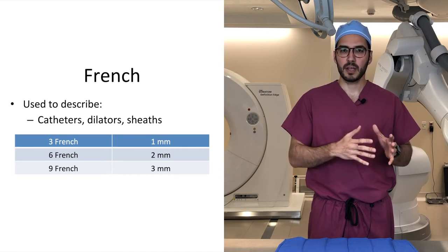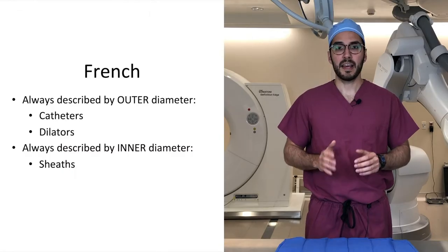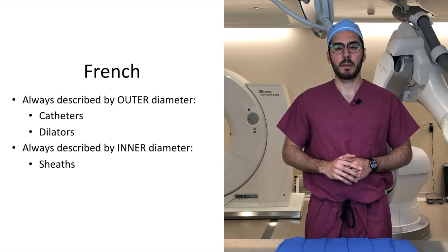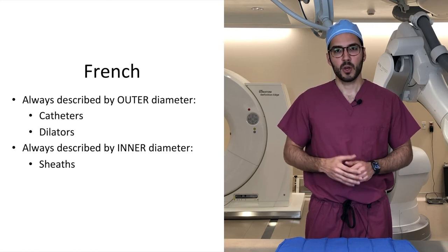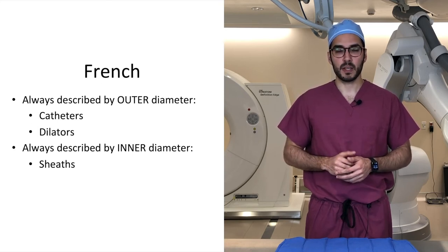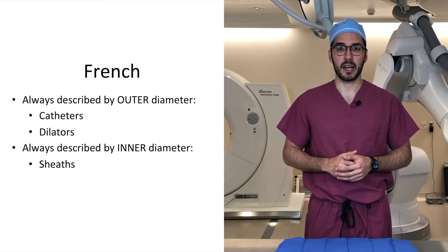So a 9 French catheter is 3 millimeters. When using the French sizing system, it is important to understand the concept of inner and outer diameter. The inner diameter describes the intraluminal diameter of a catheter, dilator, or sheath, whereas the outer diameter describes the intraluminal diameter plus the thickness of the side walls. Catheters and dilators are always described by their outer diameter, whereas sheaths are always described by their inner diameter — which makes sense, because we introduce equipment through sheaths, and it's important to know the maximum size catheter a sheath can accommodate.